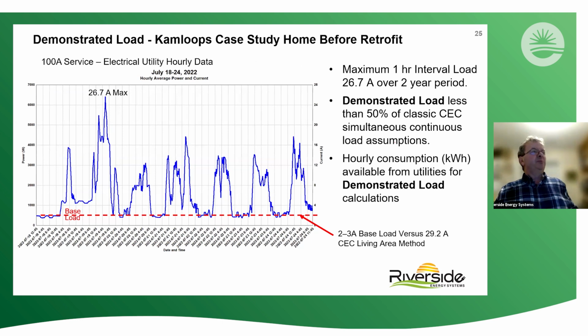So I did that for the Kamloops case study house, which has a 100 amp electrical service, as I mentioned earlier. And what I discovered was that the highest my demand was ever in the entire 24-month period I studied, actually, it was 2 years, was never higher than 26.7 amps. So certainly never exceeded 30. And when I look at the basic load, what is the lowest my load ever gets? It's way down at 2 or 3 amps, versus the 29 amps that I was forced to assume using the CEC living area method.